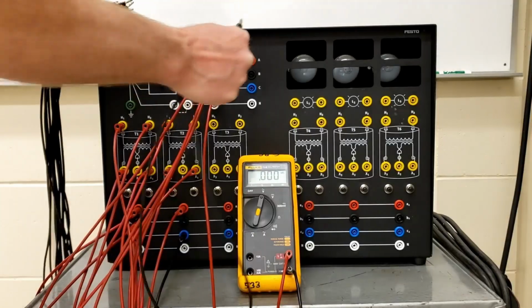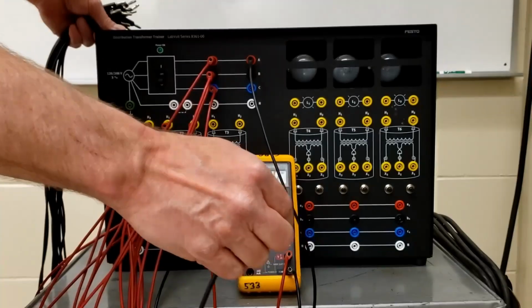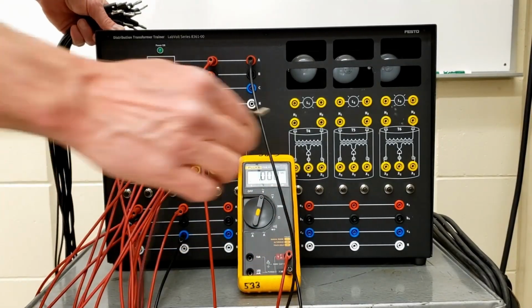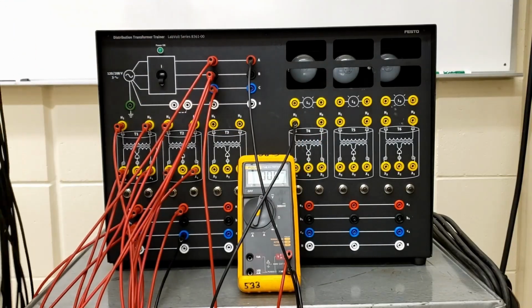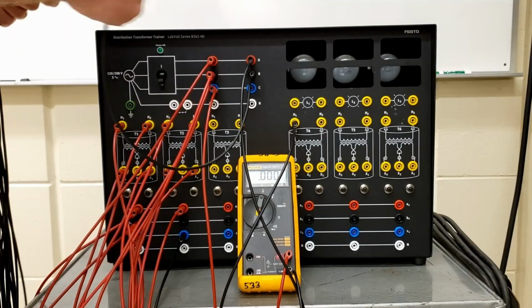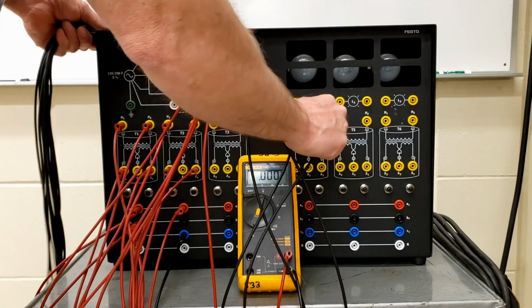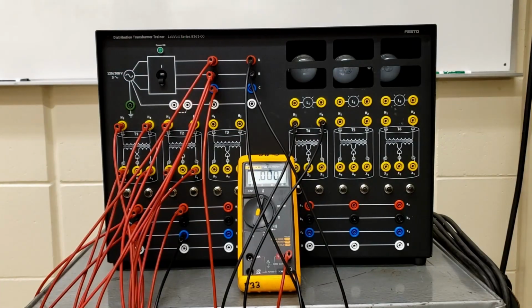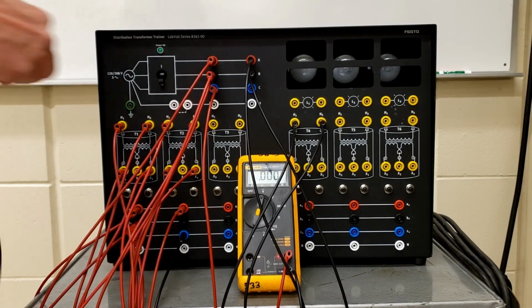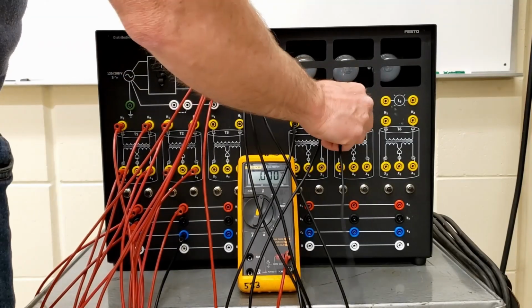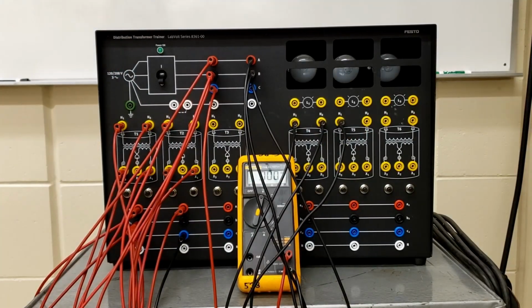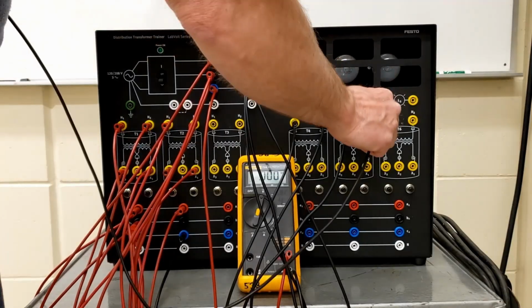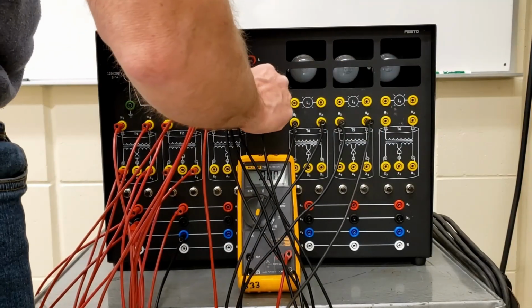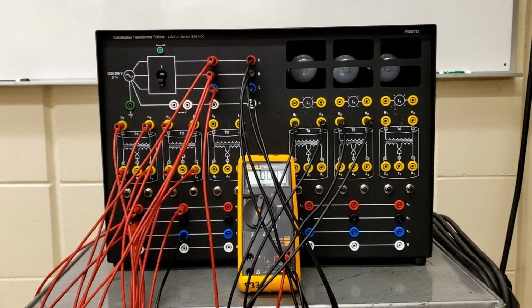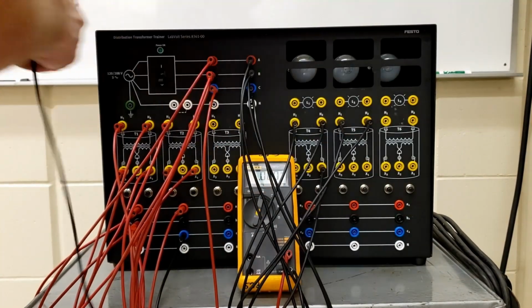So we're going to feed the primary. So the primary is going A to H1. Okay. B to H2. Okay, then on the second transformer we have H1 being fed by B. B phase feeds H1, and then the H2 goes to the C phase. Okay, looks good. Then on the secondary side there we have X1 feeding A. So X1 feeding A.